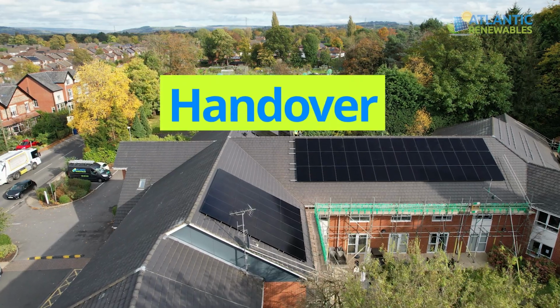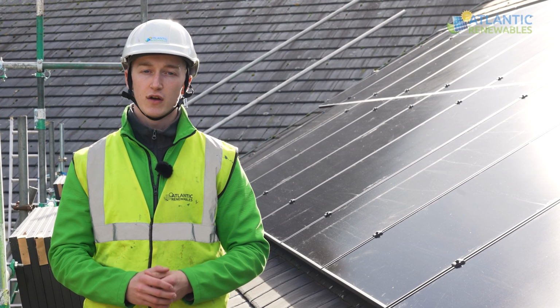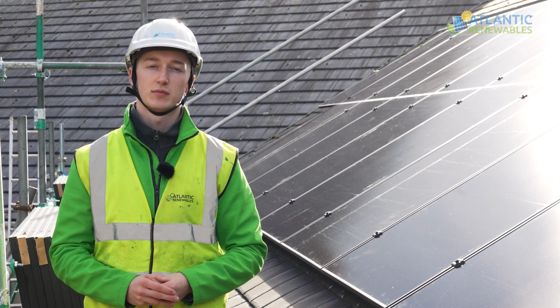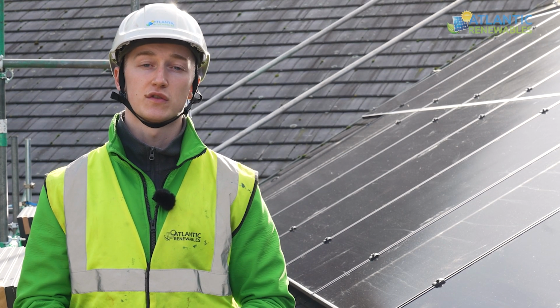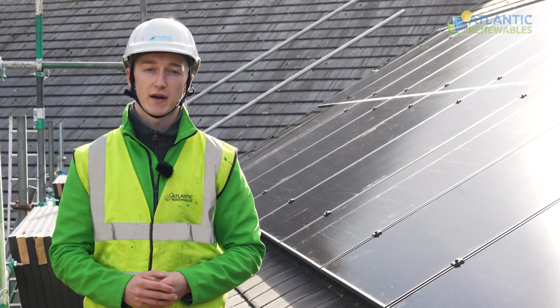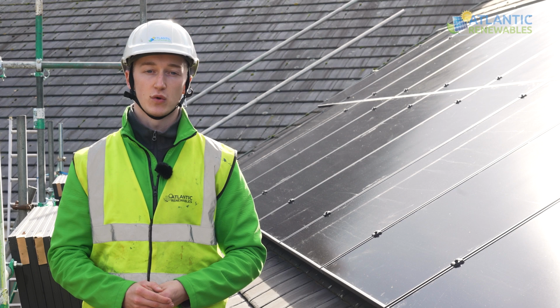In a few days when we leave site, our work doesn't stop there. We always provide a full client handover with all the paperwork that you need to set up your tariffs and your smart export guarantee as well, so you get paid for any excess solar power that you send back to the grid. As part of our service, we also provide the DC string tests as well, so you know that every single string of panels has a voltage, has a current, and therefore a power, and everything's working correctly.